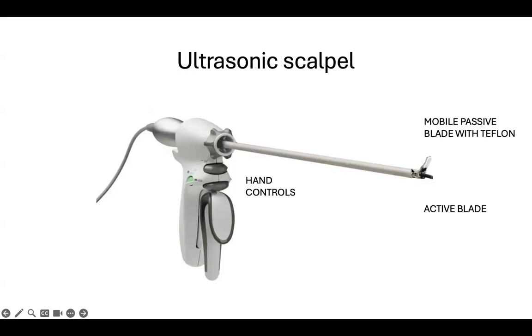Basically, this is where the entire key lies. The passive blade having the Teflon coating, the active blade which is going to vibrate. The tissue is kept in between these two blades. This active blade rubs on the tissue with support against this passive blade, and then heat is generated and the tissue gets coagulated.